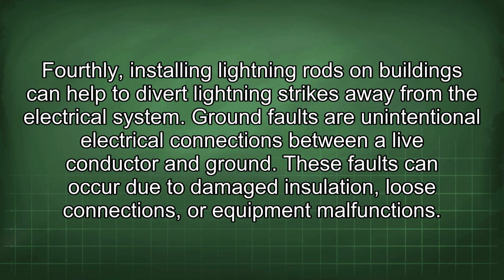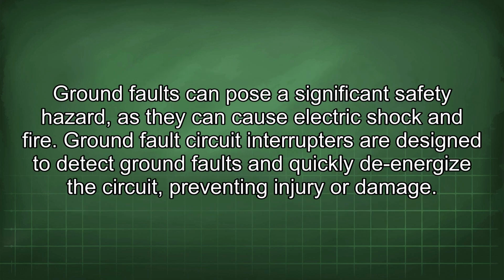Ground faults are unintentional electrical connections between a live conductor and ground. These faults could occur due to damaged insulation, loose connections, or equipment malfunctions. Ground faults can pose a significant safety hazard, as they can cause electric shock and fire. Ground fault circuit interrupters are designed to detect ground faults and quickly de-energize the circuit, preventing injury or damage.